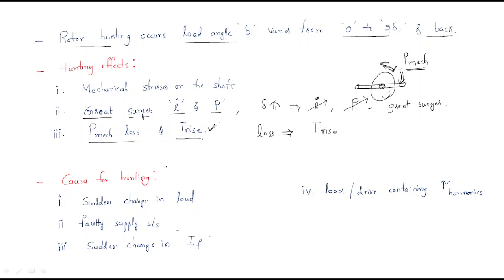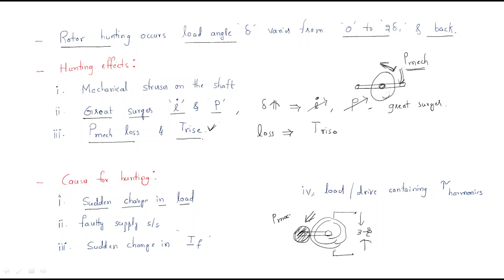The causes of hunting are as follows. First cause: sudden change in load. If the synchronous motor has a mechanical load that suddenly increases or drops to zero, surges occur and hunting develops.